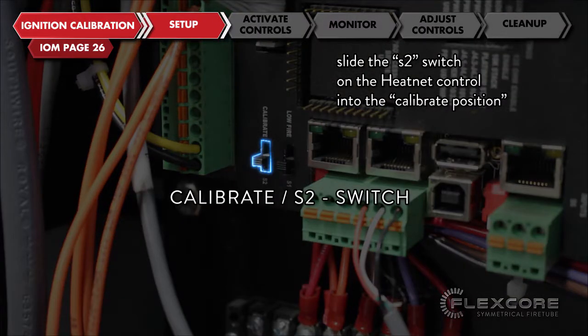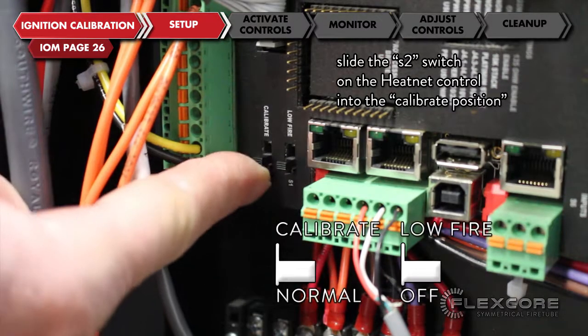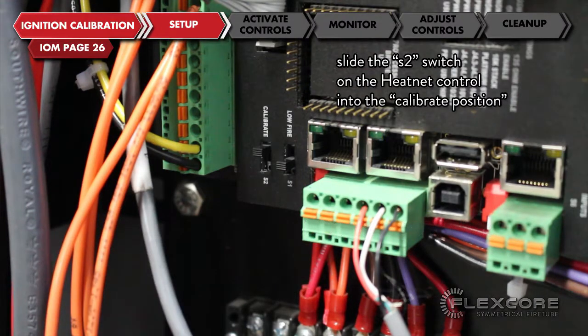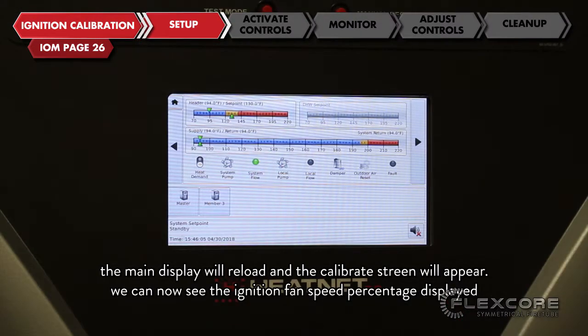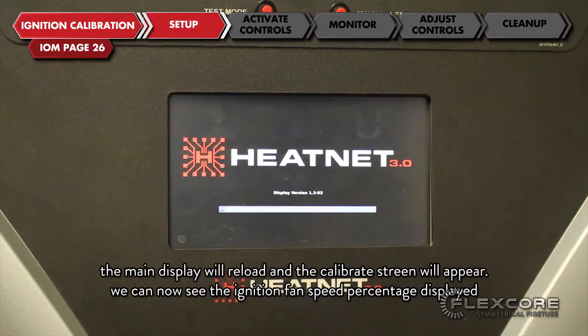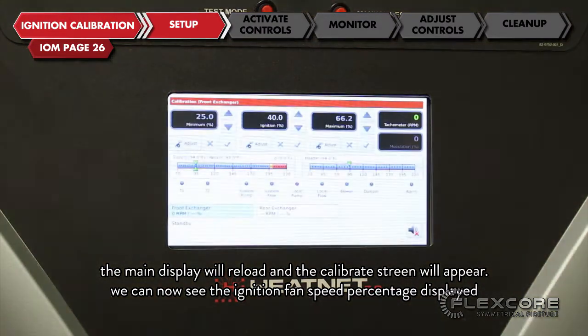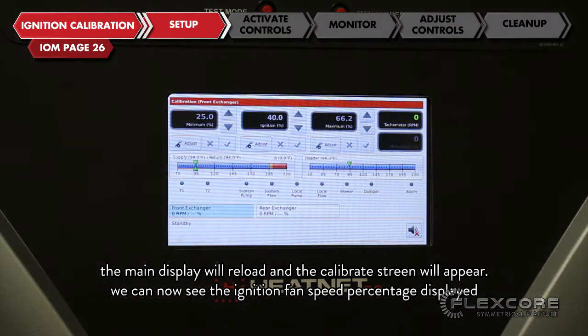Slide the S2 switch on the heatnet control into the calibrate position. The main display will reload and the calibrate screen will appear. We can now see the ignition fan speed percentage displayed.